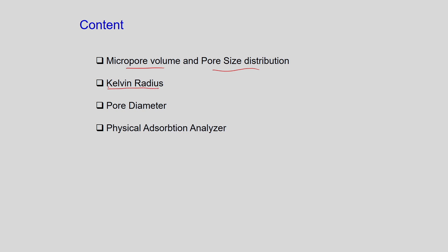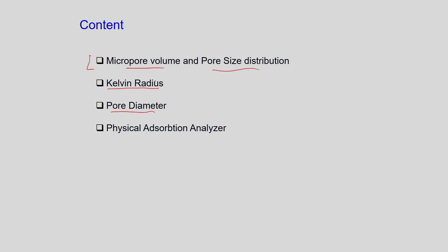The Kelvin radius is a very important concept — its significance in terms of bulk condensation will be explained in detail. These results are obtained as direct measurements of the BET isotherms. The instrument gives us the amount adsorbed at a certain reduced pressure, and from there you can measure micropore volume, pore size distribution, and Kelvin radius. Pore diameter is also a direct outcome of the BET instrument measurements. Finally, we will see a physical adsorption volumetric adsorption analyzer.